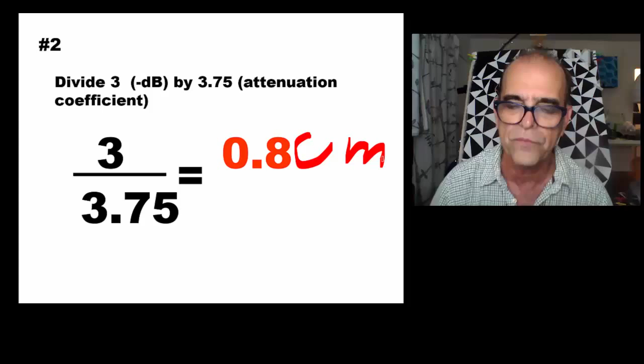And this is the important part that I want you to see. The half value layer thickness is inversely proportional to the frequency of the transducer. The low frequency transducer has a high half value layer thickness, and the high frequency transducer has a low half value layer thickness. Half value layer thickness is the penetration. When a transducer has a big half value layer thickness, it means the frequency penetrates the body. The penetration of a 7.5 megahertz transducer is not as good as 2.5, and this is the reason that even though high frequency transducers have good quality, they do not have enough penetration to scan organs deeper in the body. In resume, 7.5 megahertz is good for the thyroid, 2.5 megahertz is good for deeper organs like the kidneys.